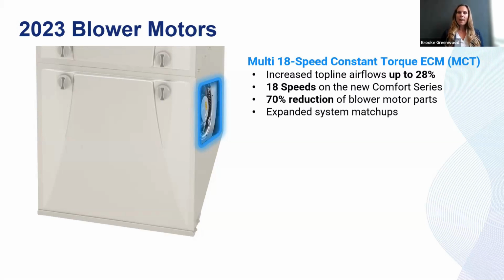We're using the full torque value of the motors from 15 to 99%. When you lay out those airflows in roughly 5% increments, you come up with 18 speeds. So doubling the speeds works, but that's the actual math behind how we got to 18 speeds.